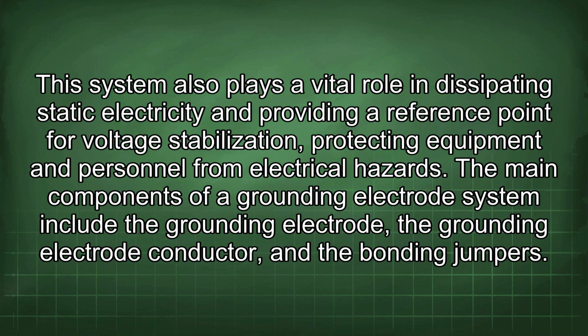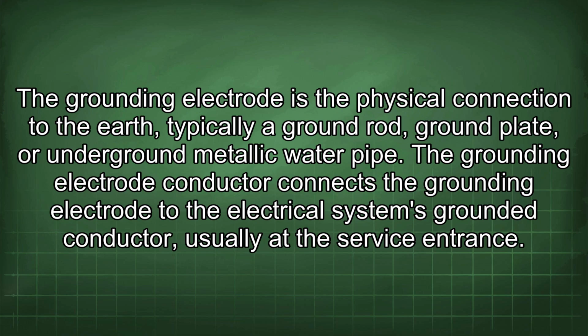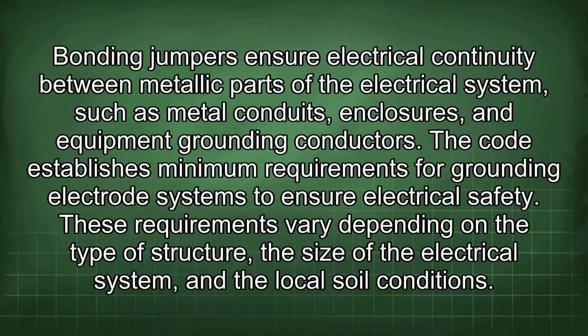The main components of a grounding electrode system include the grounding electrode, the grounding electrode conductor, and the bonding jumpers. The grounding electrode is the physical connection to the earth, typically a ground rod, ground plate, or underground metallic water pipe. The grounding electrode conductor connects the grounding electrode to the electrical system's grounded conductor, usually at the service entrance. Bonding jumpers ensure electrical continuity between metallic parts of the electrical system, such as metal conduits, enclosures, and equipment grounding conductors.